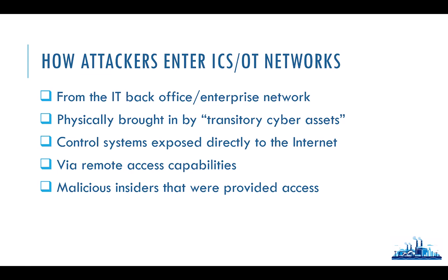It's also common to see malware brought into the environment by what they call in the ICS world 'transitory cyber assets' — really these are USB drives and laptops. Somebody can bring in an infected USB drive and plug it into a system on the OT network. Or a vendor comes in to do maintenance, they bring in their laptop, and if that laptop is infected and they plug it into the OT network, that infection can potentially spread.